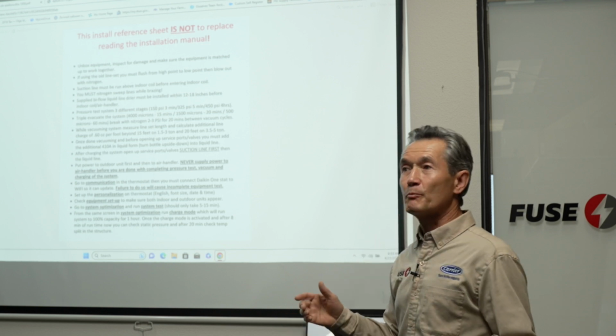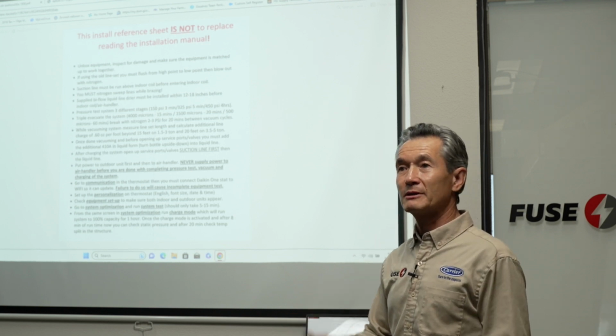While vacuuming the system, you need to calculate whatever required Freon charge needs to be done. All the equipment comes pre-charged. We know about it, right? From 1 to 3 ton is a certain amount, from 3 to 5 a little bit higher. And we'll talk about it. It's on the table. It's easy to calculate, but it has to be done during your vacuum because you're still sitting and waiting, basically. So that's why you have to do something important.